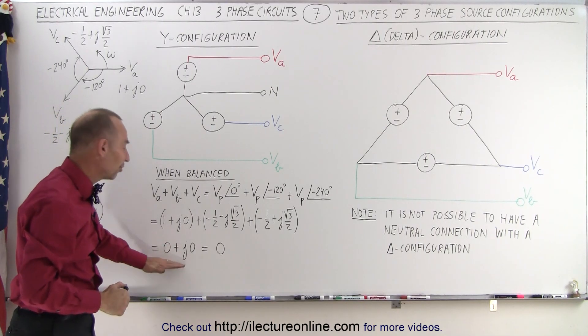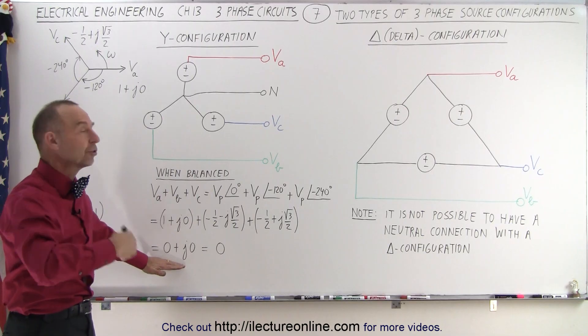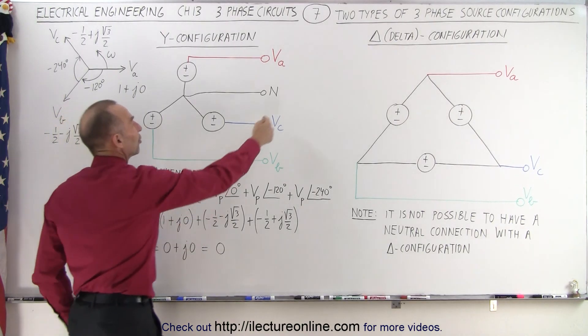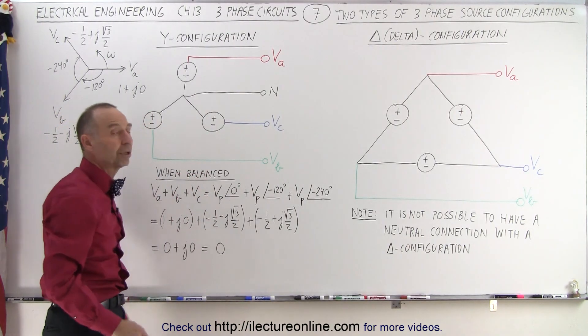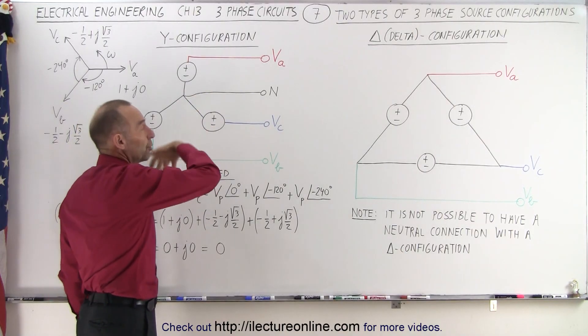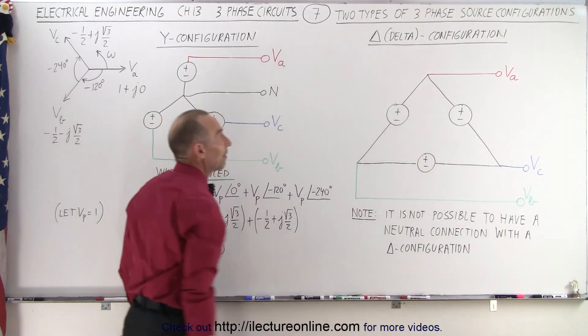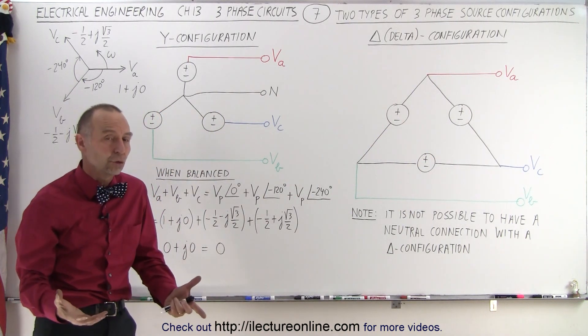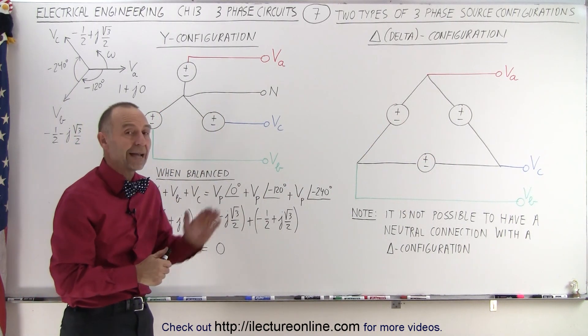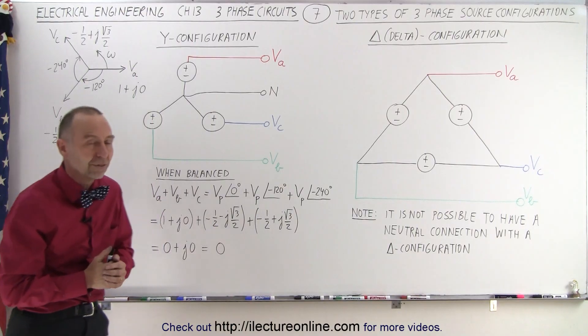But if that's the case, we have zero voltage sum of all three voltages combined, and we should have zero current coming back on the neutral in such a way that the neutral can be removed, and it should not make any difference, and therefore we could have a delta configuration with no neutral connection, and it should be perfectly fine if the system is balanced.